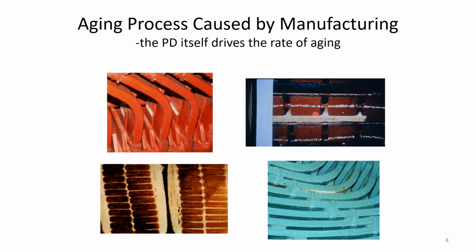Very slow failure mechanisms. In fact, rarely will they cause failure directly. They just normally cause issues if you have ozone, and then ozone causes water leaks in your heat exchangers, or causes your bearings to fail, or retaining rings to blow apart. And all of those are real experiences that people have had.